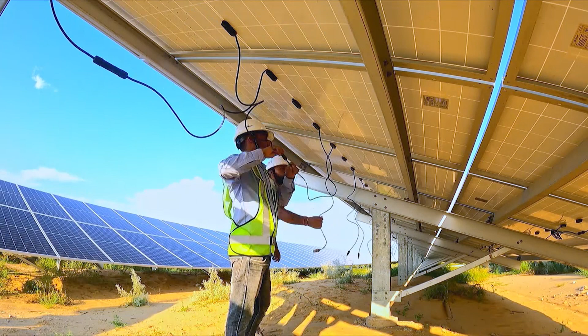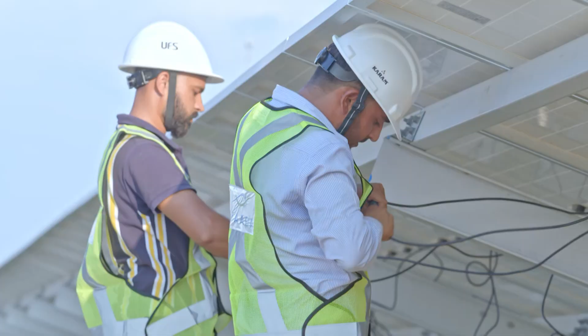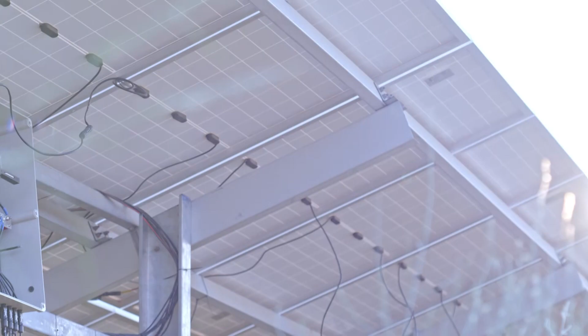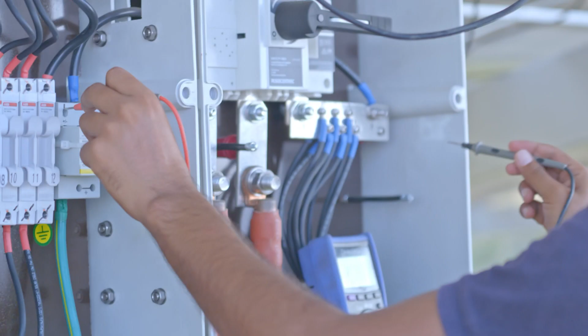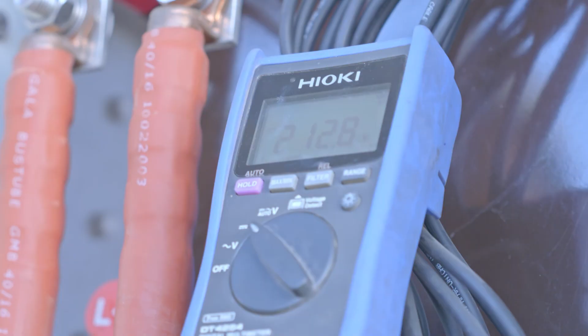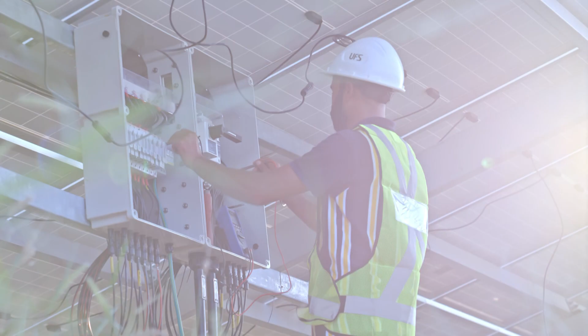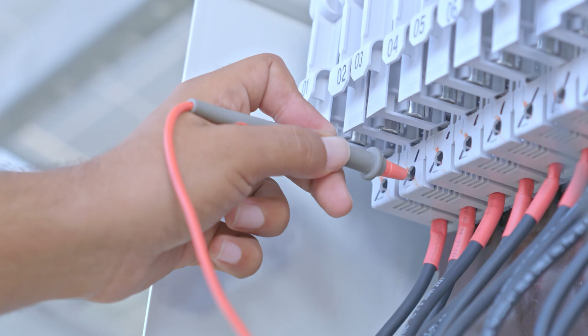With millions of modules, the current first needs to be combined from the individual modules before it travels ahead. The string combiner box is used for this job. Current from 30 solar modules travels to a single string combiner box. A string combiner box strings together the output from various modules. It is essentially a monitoring device. It is used to monitor the current, voltage, and total power. 11 such string combiner boxes combine the current further and send it to an individual inverter.